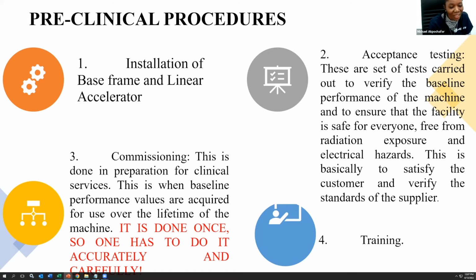A lot of tests are carried out. Then reproducibility test, the light field, a lot of tests like that, just to ensure that the performance specification is met. And also during this acceptance testing, there is need for what we call radiation monitoring. You have to monitor the environment to ensure that by the time the accelerator is being put into use, the environment is safe for everyone to work. So that is what we do during acceptance testing. This is a very important test. Now, after this acceptance testing, before our commissioning starts, we do absolute dosimetry.